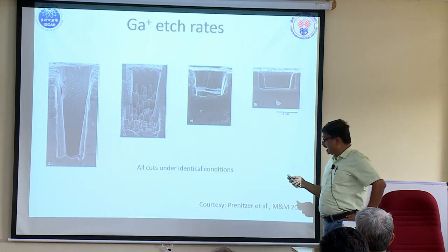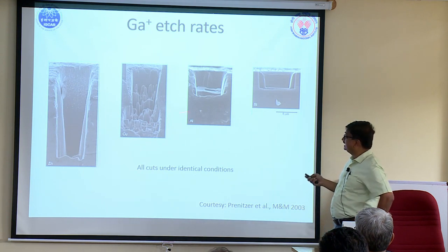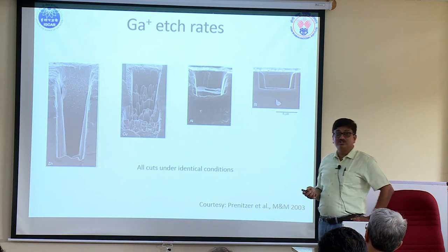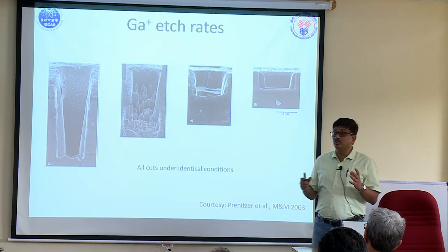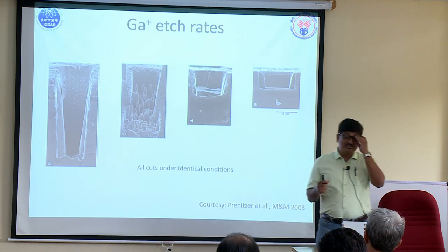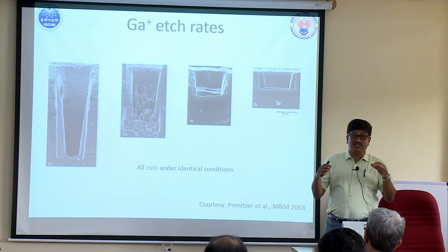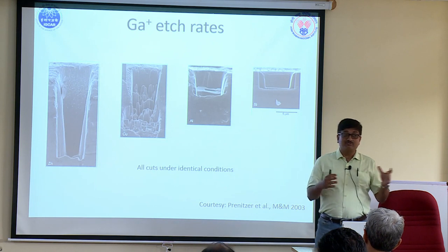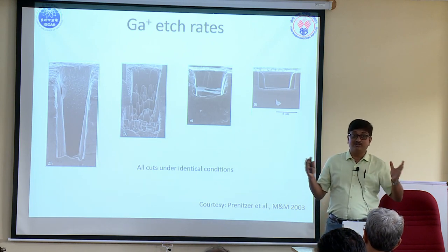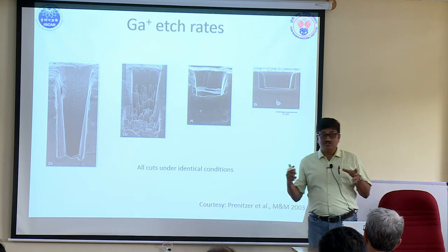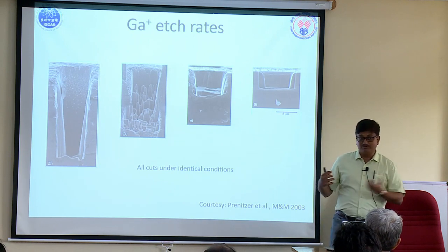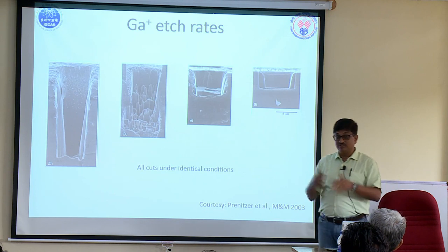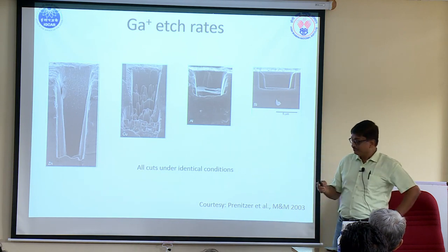You see, covalently bonded silicon is very clean, there is no problem at all. But once you start using copper or zinc, you have a lot of these kinds of curvatures. These are actually redepositions. It depends on your pumping system. These features will depend on the microscope, from the Zeiss to the FEI, and on the number of IGPs that you are inserting into the gallium column, very simple. FEI always puts one more IGP 4, which is very useful. If you are using a Zeiss machine, you will see more of these redepositions.